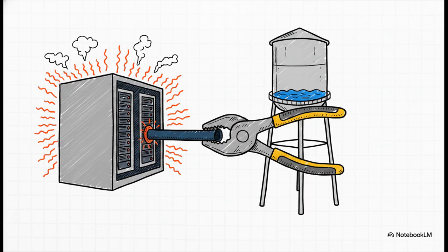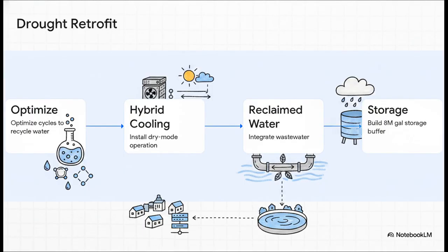They were quite literally facing server shutdowns if they couldn't adapt fast. So what did they do to avoid a total operational disaster and stop stressing the town? Engineers rapidly rolled out a 4-step hydrologic mitigation strategy. First, they optimized their water chemistry to recycle water more efficiently. Second, they retrofitted hybrid cooling, letting the plant run in a dry mode when the weather cooled down. Third, they started piping in reclaimed wastewater.